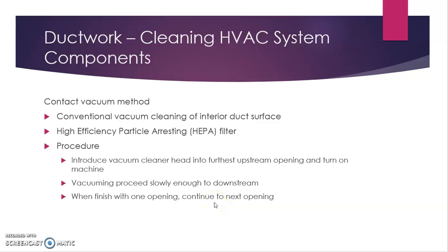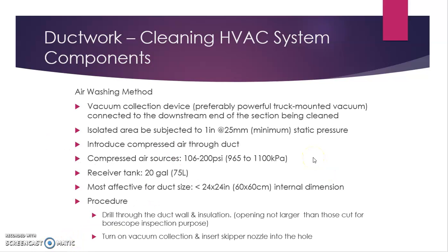So the vacuum will proceed slowly to the downstream, or the nearest place, which is the location of the opening of our ducting system. When finished with one opening, we go to the next opening. It means we usually do it by part, one ductwork system at a time, and when we finish one, we go to the next ductwork system. So it goes one branch to one branch. The next one is the air washing method. This is also quite normal.